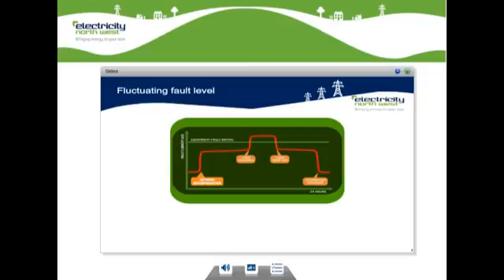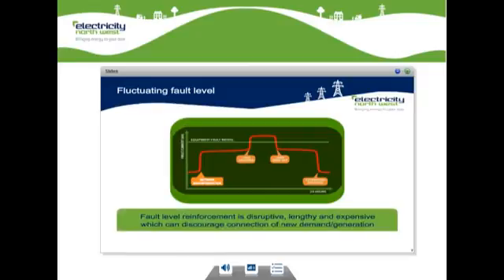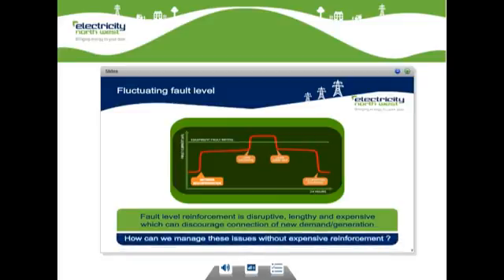equipment can safely perform. Now, when we decide that the potential fault current is larger than the rating of any of the equipment, our traditional approach is to replace that equipment with a higher rated equivalent. This reinforcement is expensive, can be time consuming and disruptive for customers. This approach also doesn't provide an accurate way of measuring fault current. So, how can we work smarter, predict fault current more accurately, and avoid resorting to expensive reinforcement?